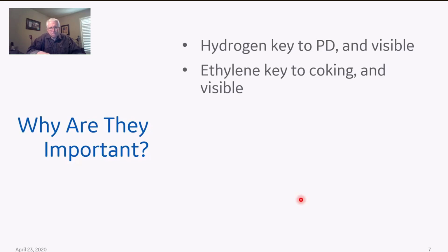In the early days of load tap changer work, we rolled crews on load tap changer DGA to locate problems that were not visible, and the crews became complacent about it. It really made it difficult, once we finally nailed how to read load tap changer DGA, to create some kind of enthusiasm. Enthusiasm is when I'm rolled out to a problem, I drain the LTC or the main tank, I open the door and look inside - if I'm not motivated, I look inside and say, well, I don't see anything going on here. There's the lack of motivation.